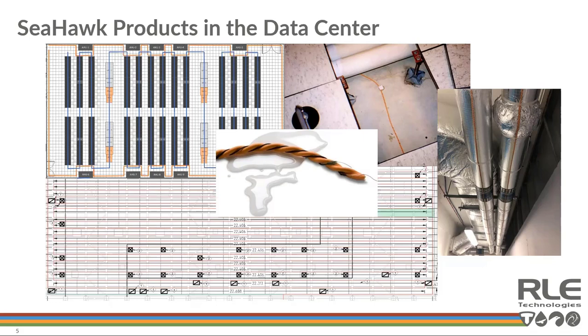We also see it as fixed overhead supply return lines to quickly identify threats before they fall into critical areas. The serpentine pattern really comes into play because if you only have a perimeter around the outside of a room, an overhead leak might take a while to spread out. But with a serpentine pattern underneath the raised floor, it's going to drip and roll, and you'll catch it much more quickly.